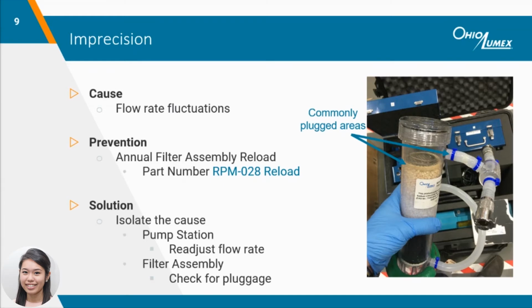Since flow rate is the determining factor for the size or area of the mercury peak, it's best to keep a steady flow rate to maintain precision. A flow rate at 1 liter per minute will yield a peak 4 times larger than that at 4 liters per minute. If the flow rate fluctuates due to pluggage, the mercury passes through the optical cell at varying rates and can cause inconsistent peaks for the same expected mass, otherwise known as imprecision.